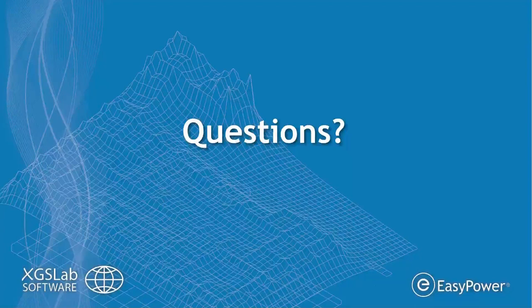So that's something that XGS Lab would be able to incorporate into the analysis. Essentially, what you're doing with the software is you're setting up the geometry of the modeled environment, telling it the electrical properties it should have, how much load there's going to be going down each of those phase conductors, and then the software will calculate how much inductive current voltage is going to be occurring at everything that could be a recipient: shield wires, pipelines, railroads, and other things, as well as some of your mitigation efforts, like that counterpoise we talked about.